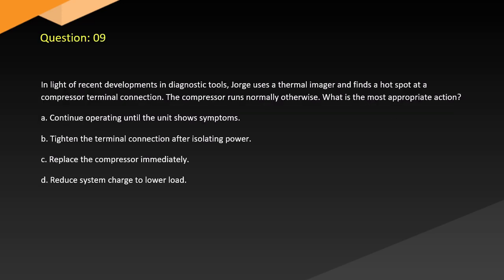Question 9. In light of recent developments in diagnostic tools, Jorge uses a thermal imager and finds a hot spot at a compressor terminal connection. The compressor runs normally otherwise. What is the most appropriate action? A. Continue operating until the unit shows symptoms. B. Tighten the terminal connection after isolating power. C. Replace the compressor immediately. D. Reduce system charge to lower load.